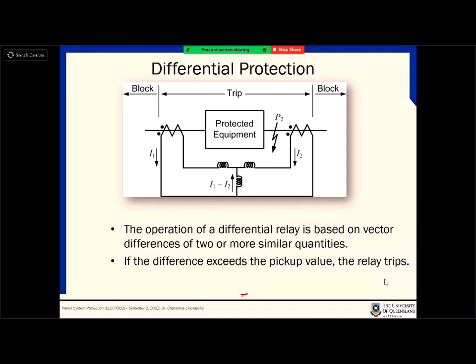So far we discussed different mechanisms to identify fault currents, and another technique is called the differential protection scheme, which also identifies fault currents. In the previous two techniques, we identified faults when the current magnitudes are high compared to the load current, by looking at current magnitudes or the impedance of the system in front of you. Low impedance means there should be some problem, and a high current in the system.